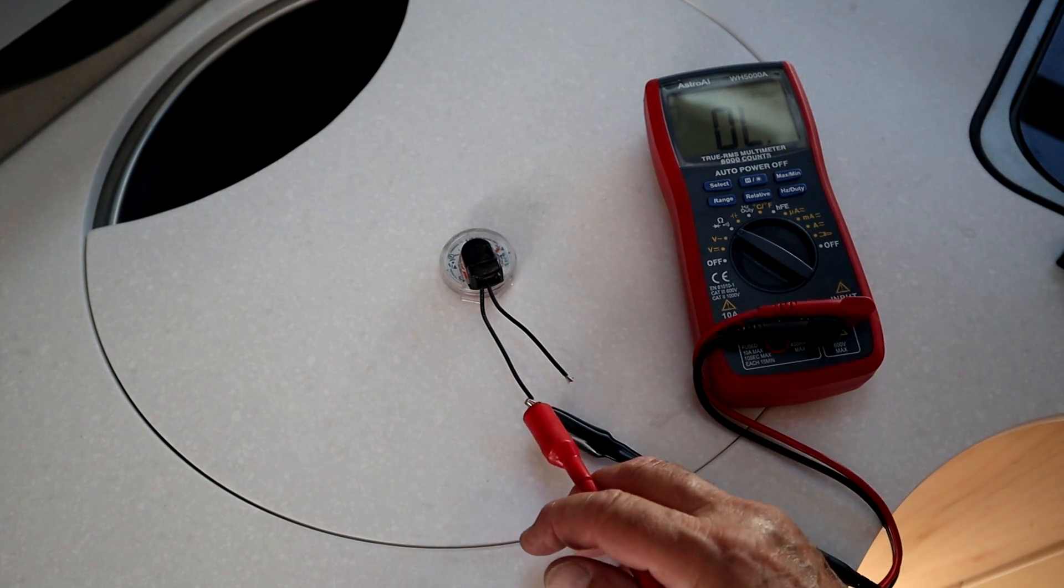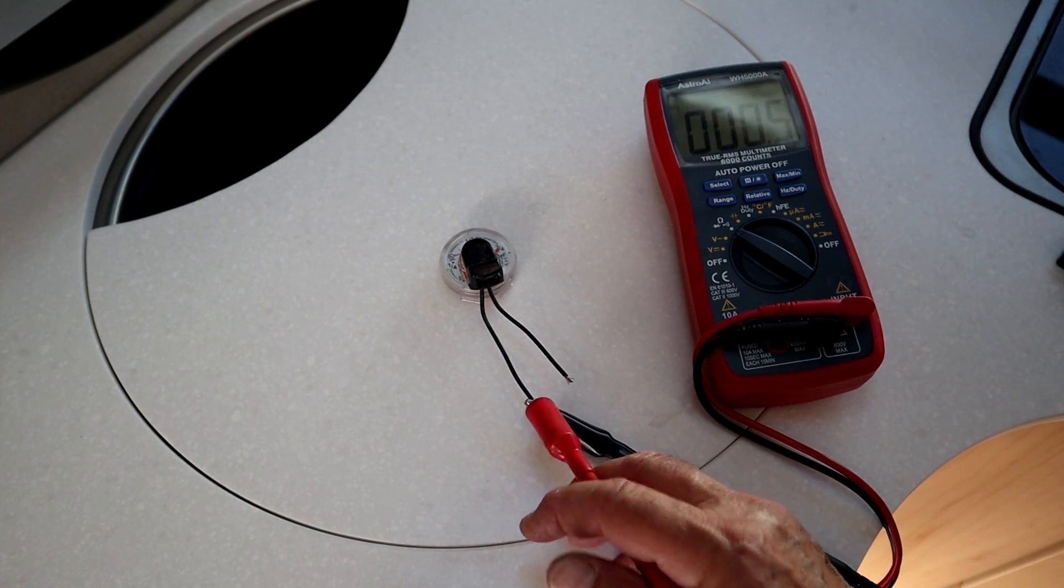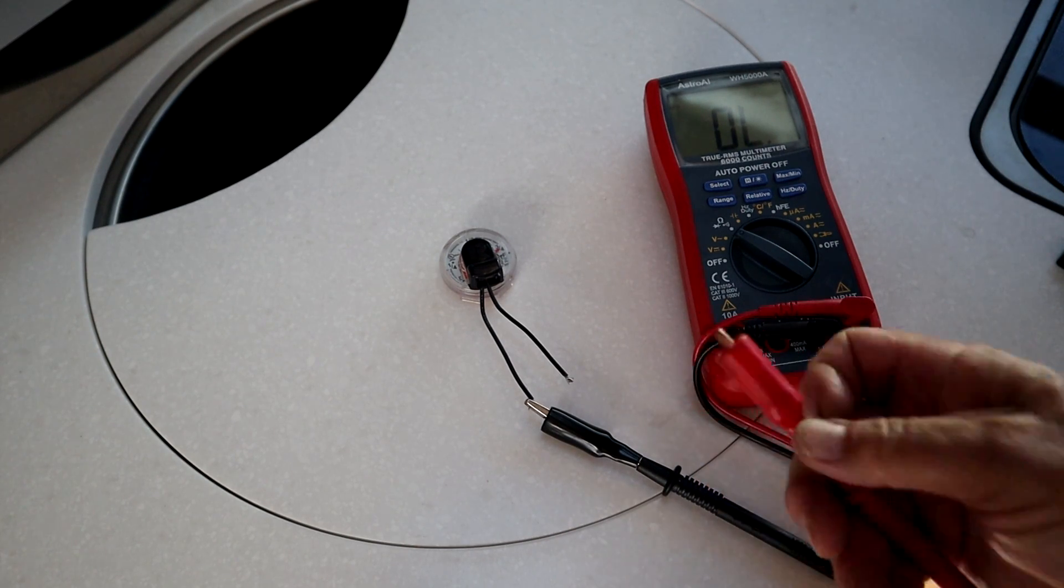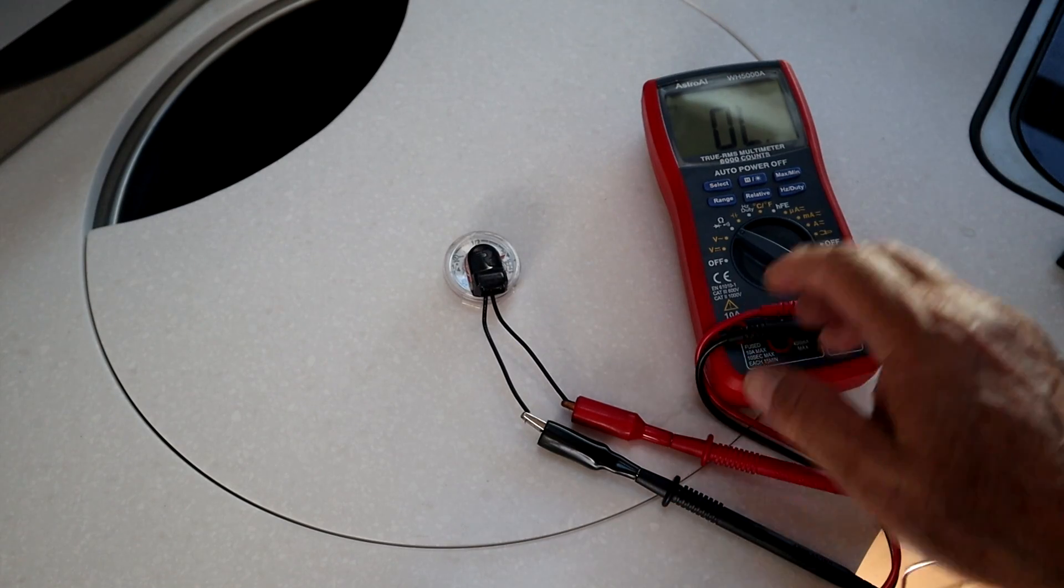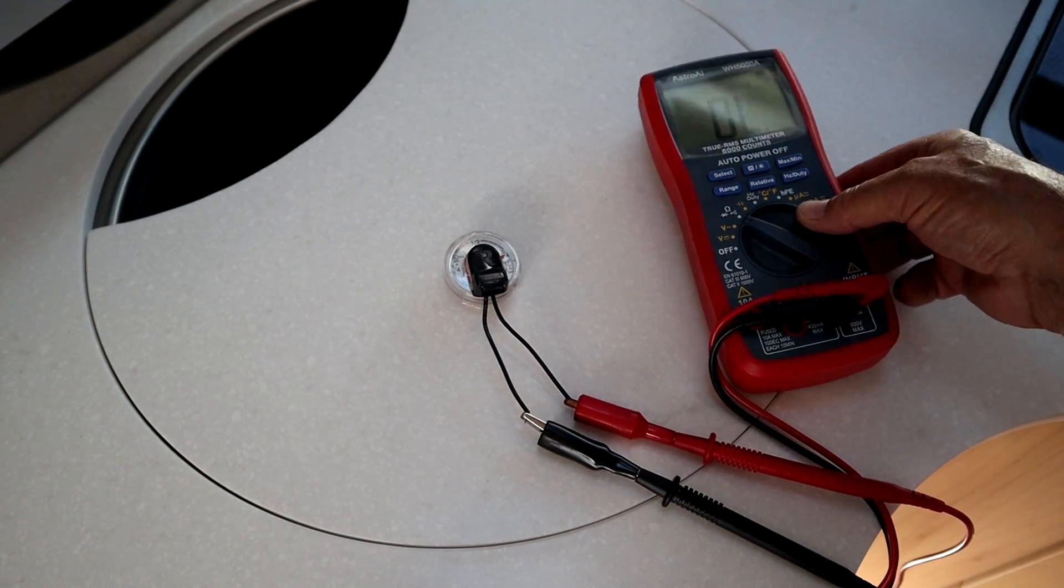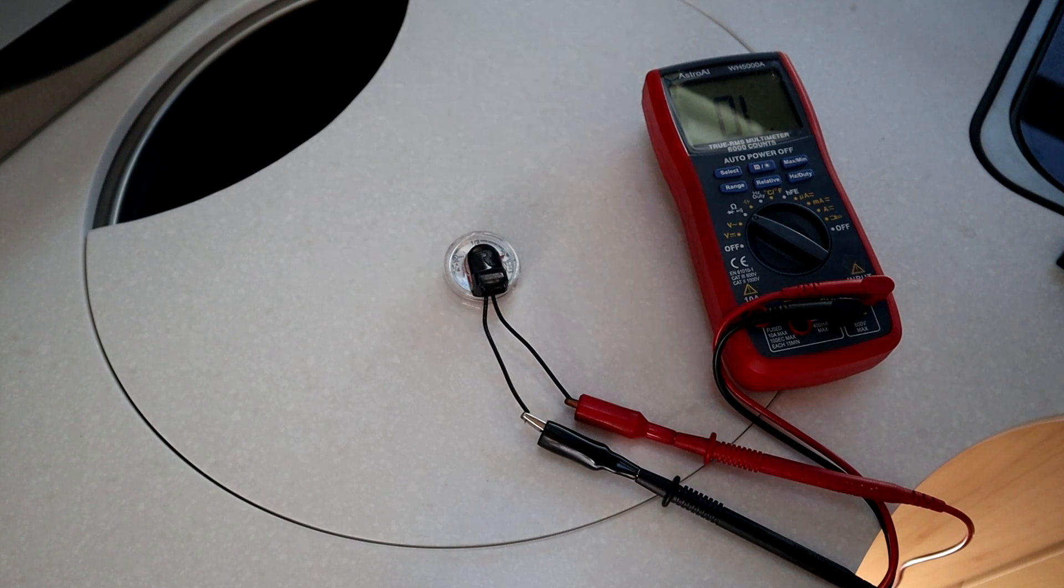Okay, using an ohm meter, we can see that this sensor that I took off is, in fact, defective. You see that it's an open circuit, and so the thin film sensor in there is defective, probably burned out.